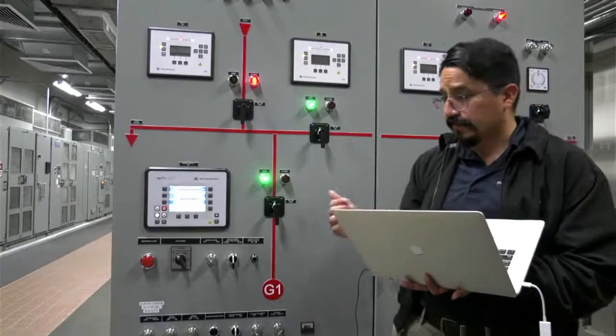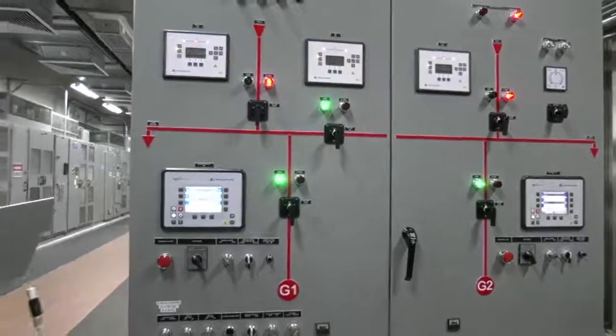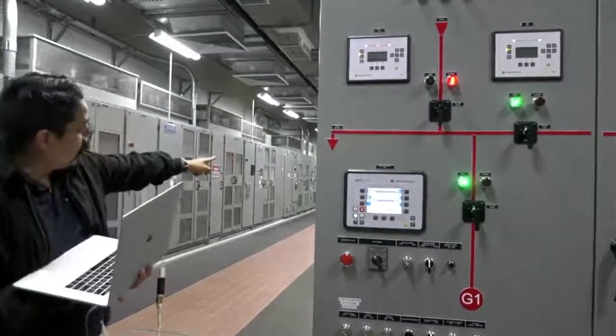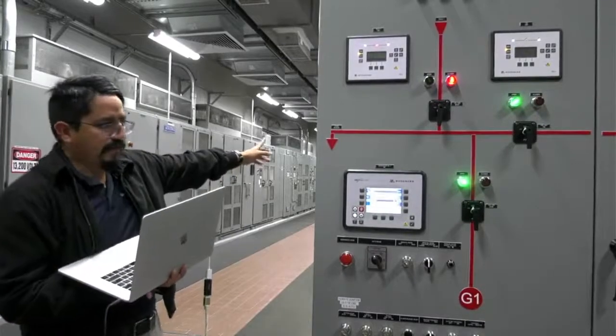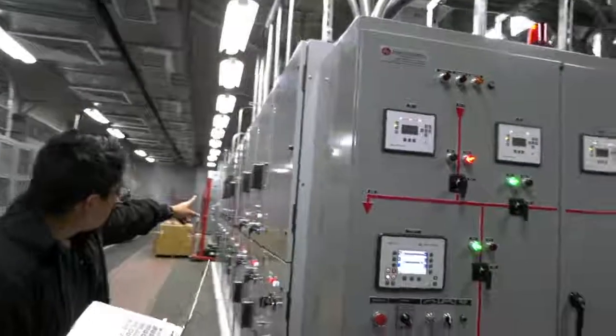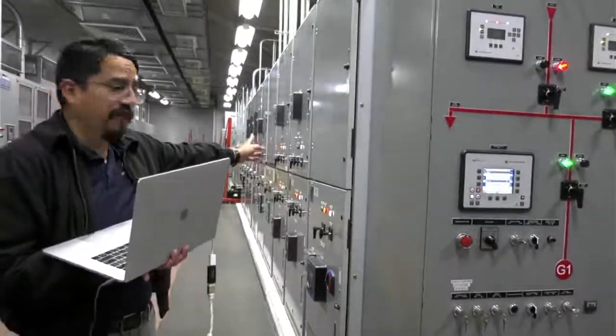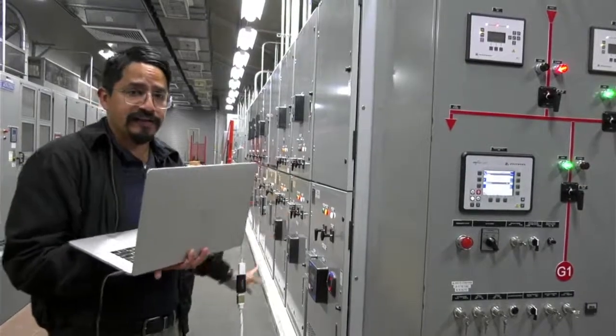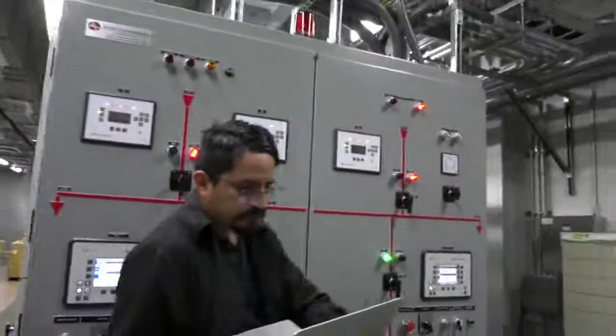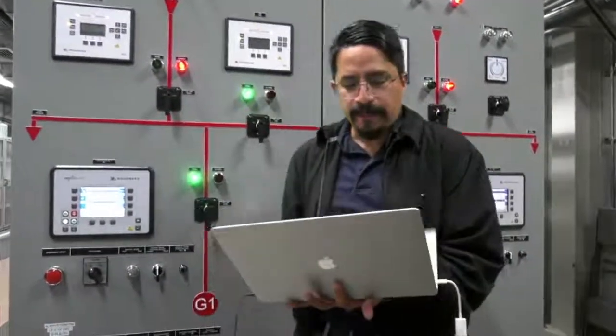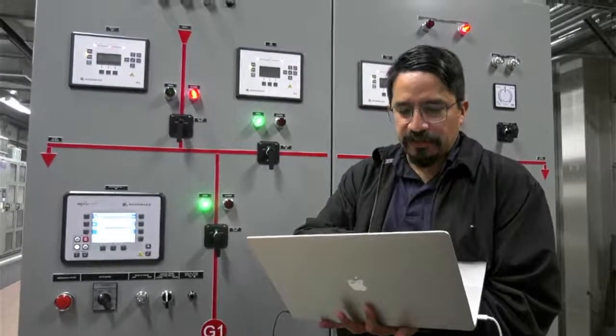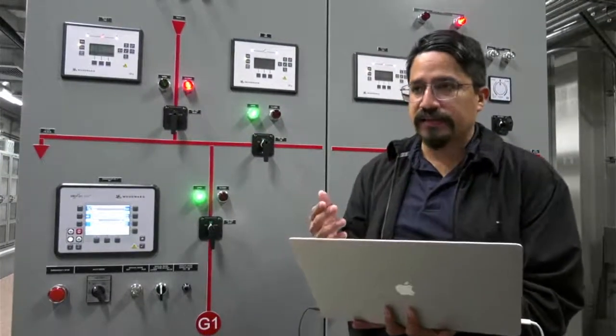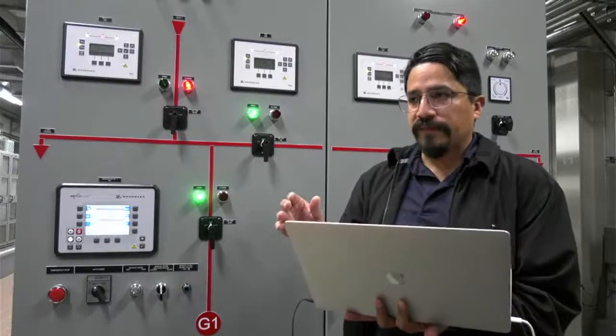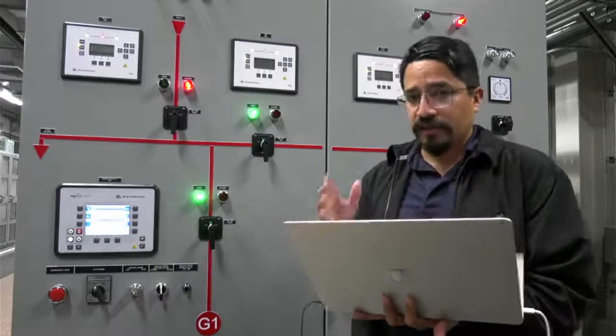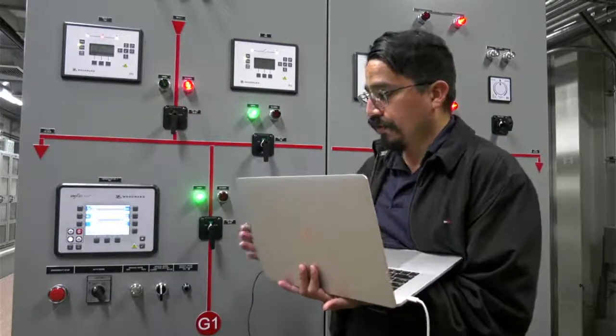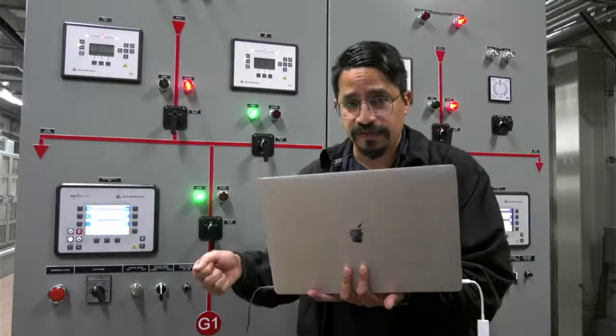The protection relays are on the back. I don't know if you can show here. We have all those relays on the back, and if we have any failure on those relays, the system is not going to do any automatic operation, because that means there is a dangerous situation. Also in manual, the closing of the circuit breaker should be initiated by an operator. That means that, in manual, if there is a blackout, the generators are not going to start by themselves. We need to go here and initiate the running of the generators.